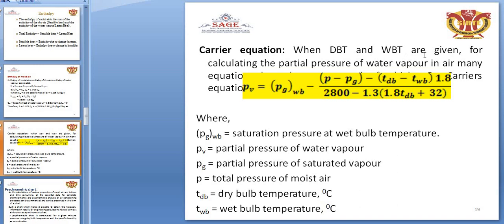When DBT and WBT are given, we use the Carrier equation to calculate the partial pressure of water vapor: P_V = P_G(wb) minus (P minus P_G(wb)) times (T_db minus T_wb) times 1.8 divided by 2800 minus 1.3 times (1.8 × T_db + 32). Here P_G(wb) is the saturation pressure at wet bulb temperature, P_V is the partial pressure of water vapor, P is total pressure, T_db is dry bulb temperature, and T_wb is wet bulb temperature.